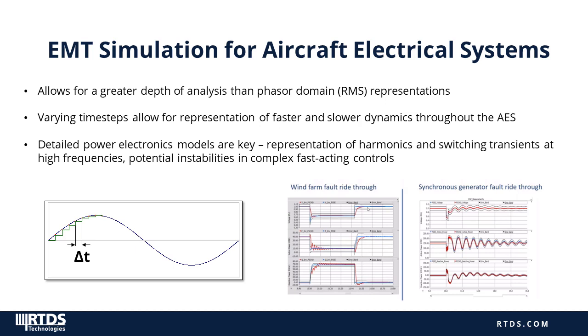In today's demo, you'll see an EMT — electromagnetic transient — simulation of the aircraft electrical system. The output of an EMT simulation is a time-varying instantaneous value; the simulation output resembles the voltage or current waveform as if measured with a scope. The frequency bandwidth that can be accurately represented is determined by the simulation time step, or delta-t. Typically that's between 25 and 50 microseconds, but it can be as small as 1 to 3 microseconds for power electronic circuits. This type of simulation allows for representation of phenomena over a wide frequency range and can capture fast transients in the power system.